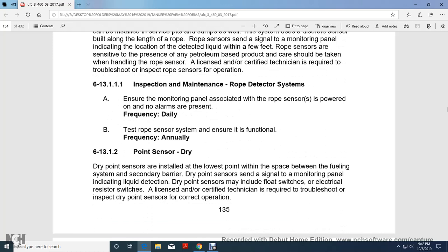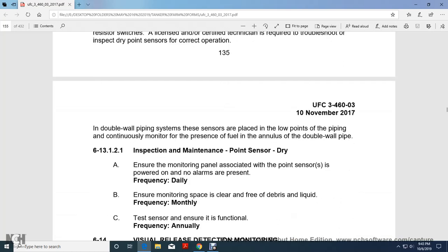Inspection maintenance of rope detector systems: ensure the monitoring panel associated with the rope sensor is powered on and no alarms are present, daily. Test the rope sensor system to ensure it is functional, annually. Point sensors: dry point sensors are installed at the lowest point of the space between the fueling system and the secondary barrier. Dry point sensors send a signal to the monitoring panel to indicate liquid detection. Dry point sensors include float switches and electrical resistors, and a licensed or certified technician is required to troubleshoot and inspect them for correct operation.